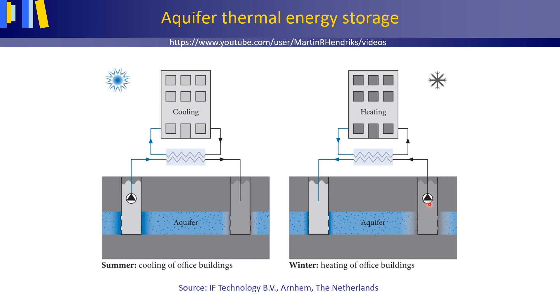The warm water is used for heating the building using its central heating system via a heat exchanger. The water that has cooled during the heat exchange process is again returned to the aquifer, now for later use in summer, and so on.